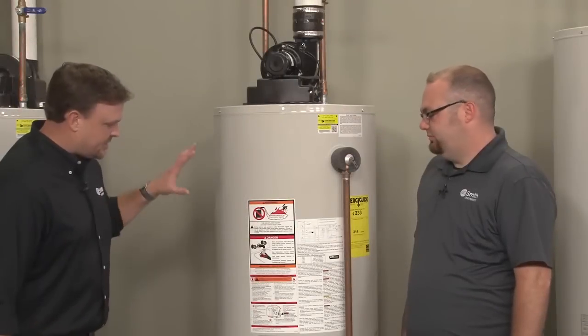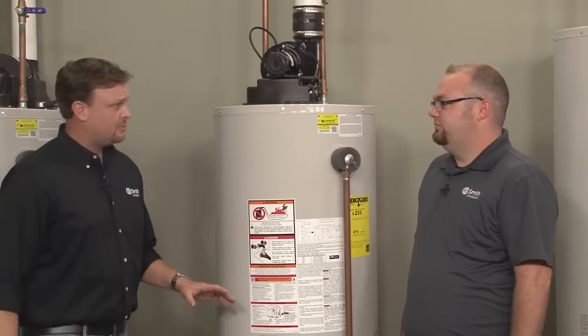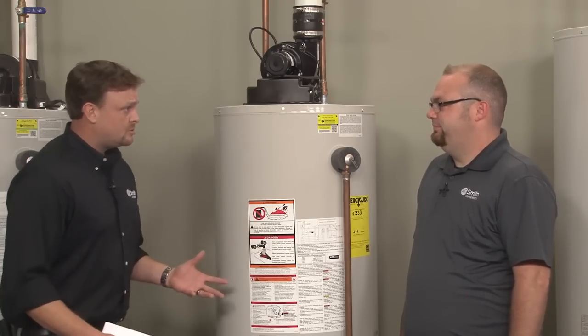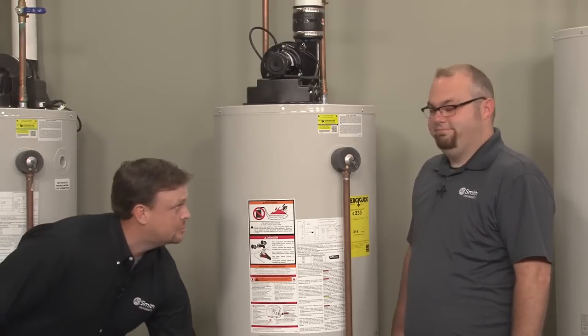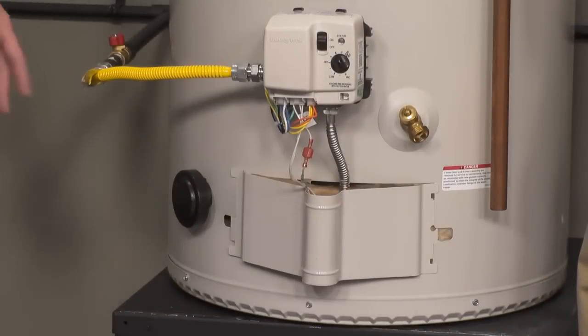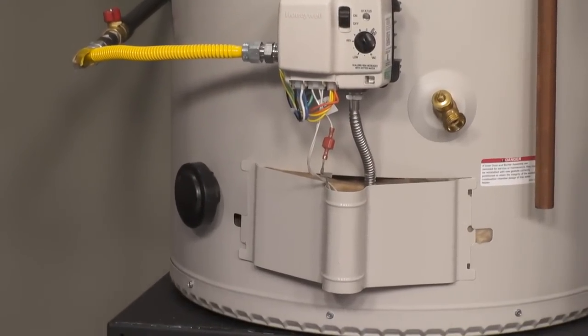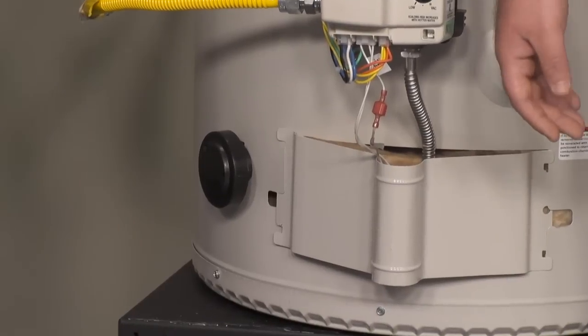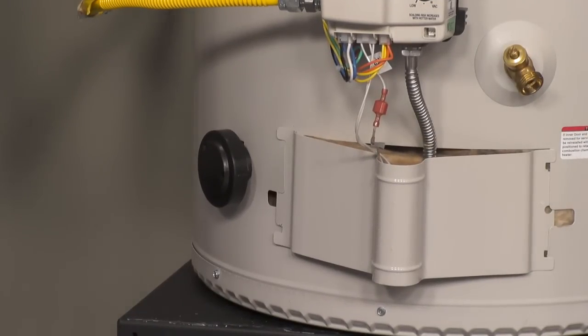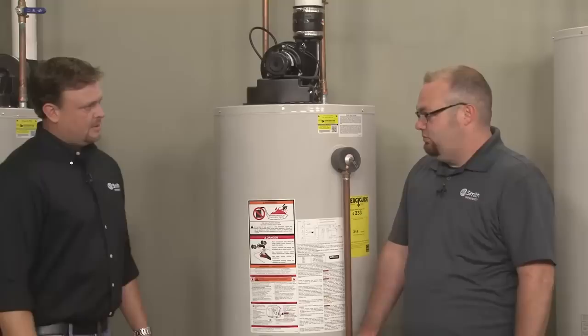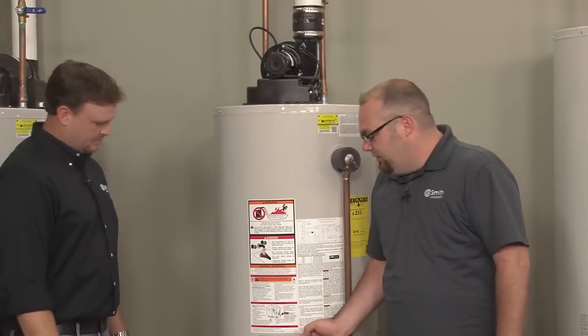There is a change, and it has to do with the flammable vapor sensor. I know on the older models it was in the front, it was on the bottom, it was close to the ground. This one's changed. We've got a different location. Yeah, on the flammable vapor sensor, we actually moved it up on the heater. On the old style, it was right at the air intakes at the bottom of the heater. Right. We moved it up on the heater some.